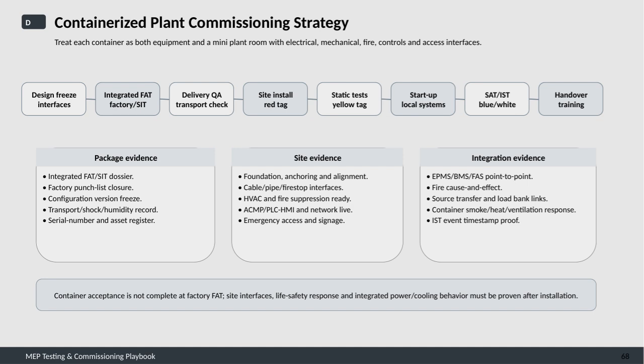Delivery quality assurance involves transport checks to ensure the container arrives undamaged. On-site installation includes red tag inspections to verify proper placement and connection. Static tests, identified with yellow tags, focus on confirming system readiness before startup, where local systems are activated and checked.